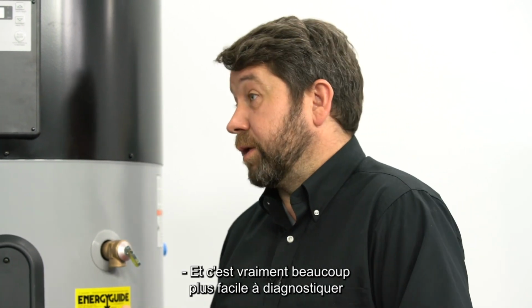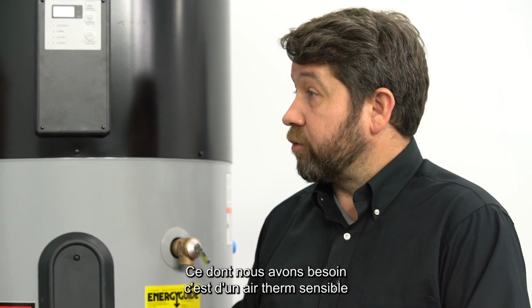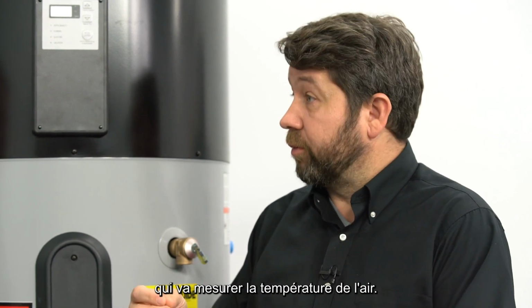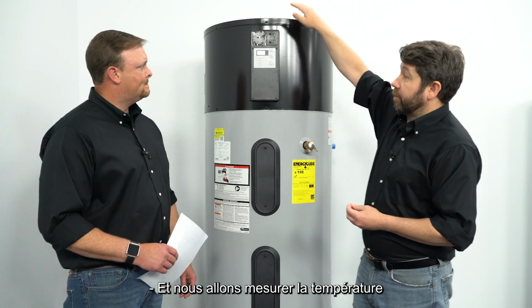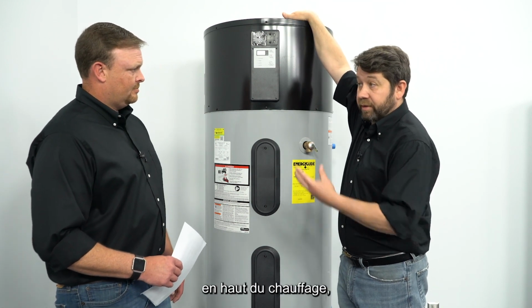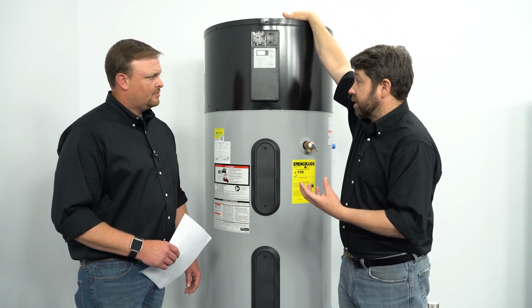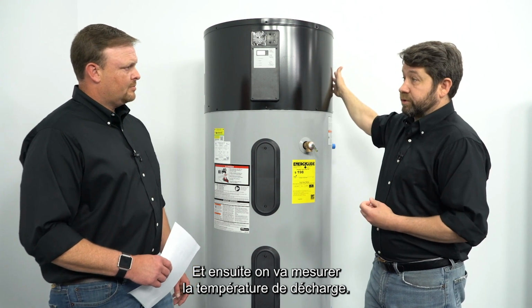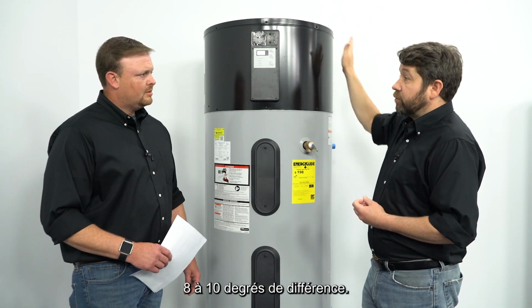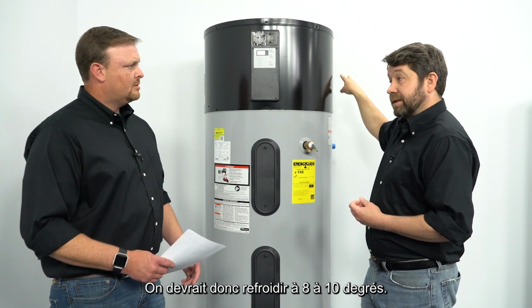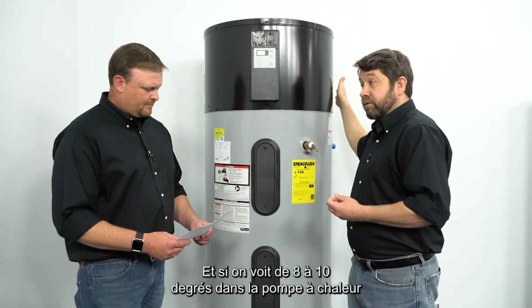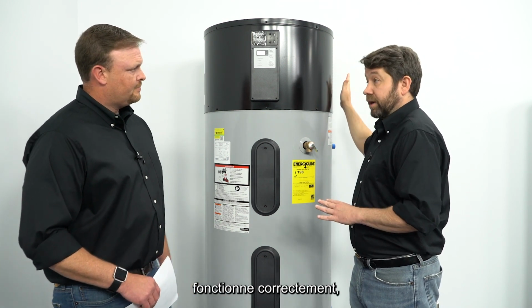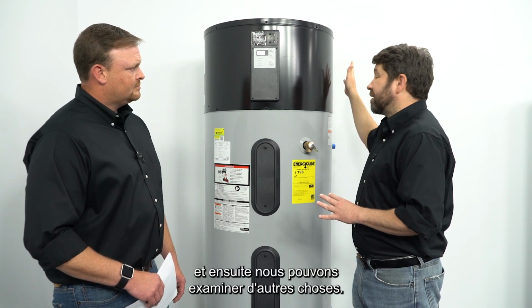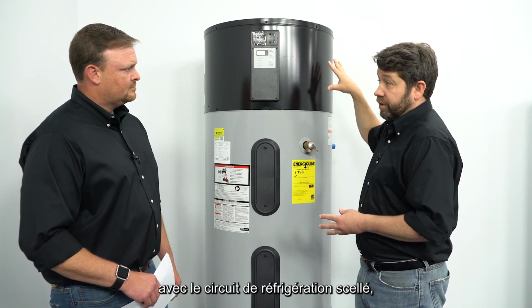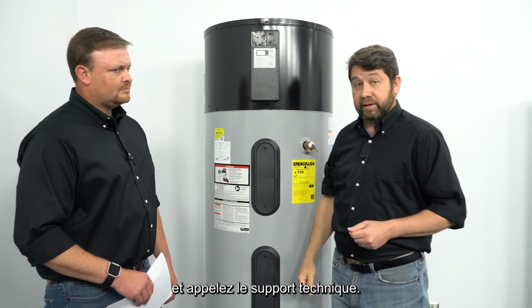Okay. And this is really much easier to diagnose than you might think. What we need is a sensible air thermometer, something that has a metal probe to measure the air temperature. We're going to measure the temperature going into the top of the heater, that air that's being pulled in, and then we're going to measure the discharge temperature. We should see 8 to 10 degrees difference between those. So we should be cooling at 8 to 10 degrees. And if we see 8 to 10 degrees, then the heat pump is operating correctly. And then we can look at some other things. If we don't, then there's a problem with the sealed refrigeration circuit, and give our folks at technical support a call.